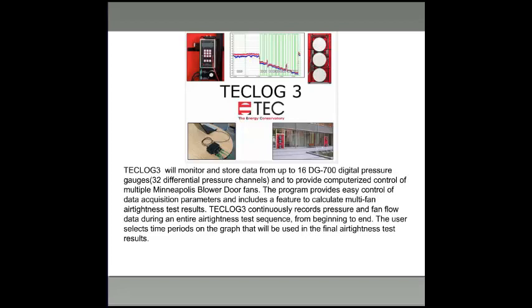TECLOG3 is our commercial testing software. It's a multi-fan software—you can connect up to 16 DG700s with 32 pressure channels and configure them any way you want. It allows computerized control of multiple blower door fans. It's really sky's the limit; whatever you can figure out that you need to do, TECLOG3 will let you do it. There's a real learning curve, so you'll want to play with it before going into the field. But once you get the hang of it, there's a lot of capability built in, and it's fully Wi-Fi enabled, so you can do hard cabling or go Wi-Fi.